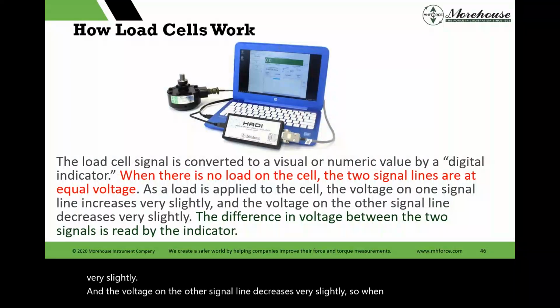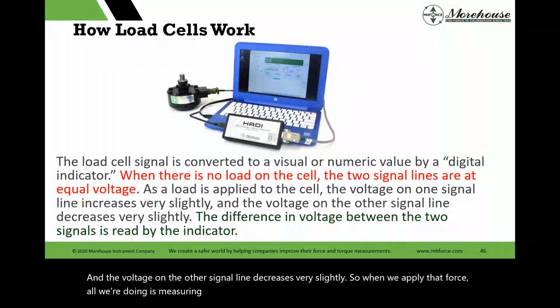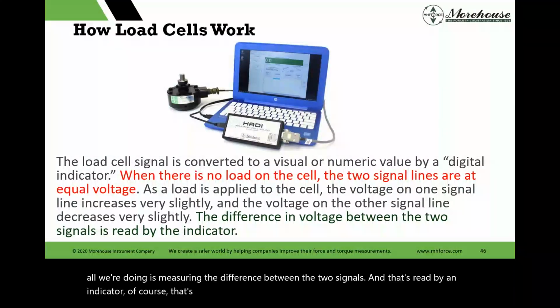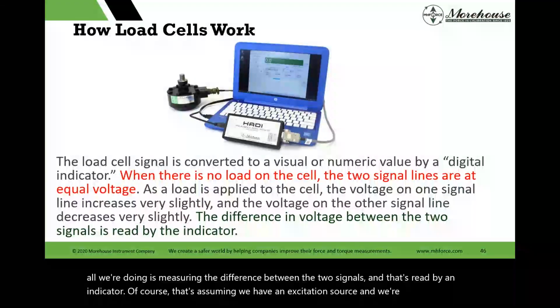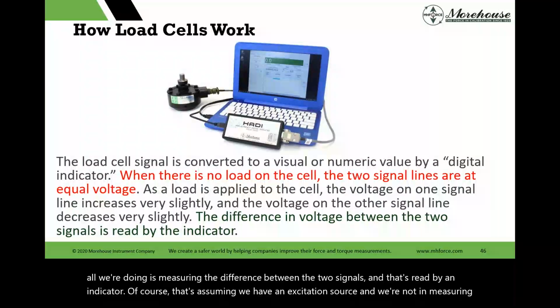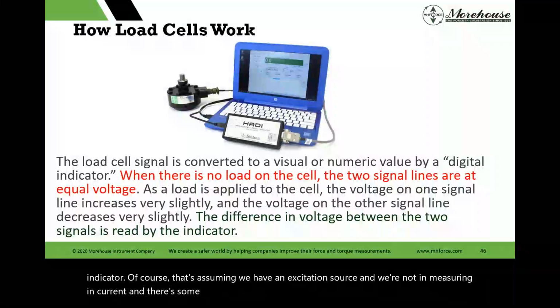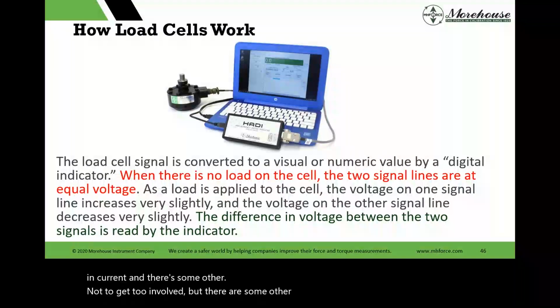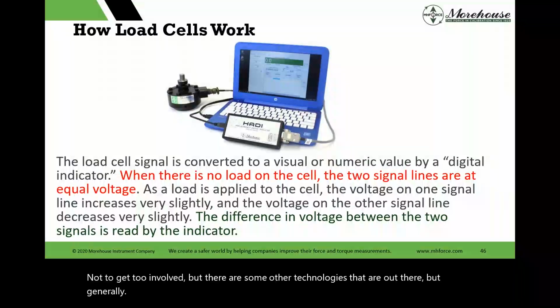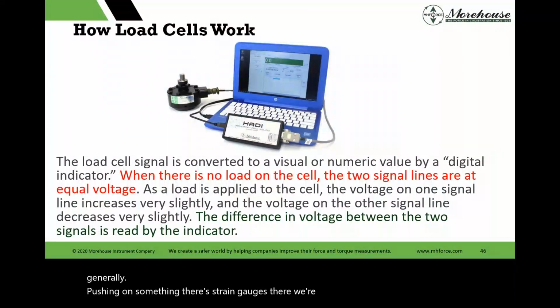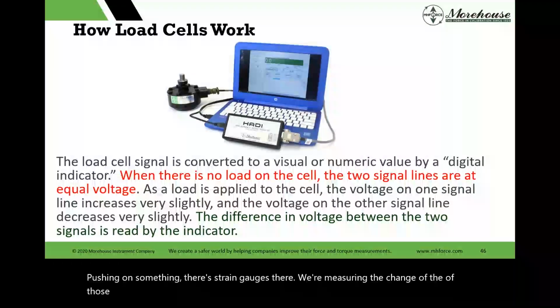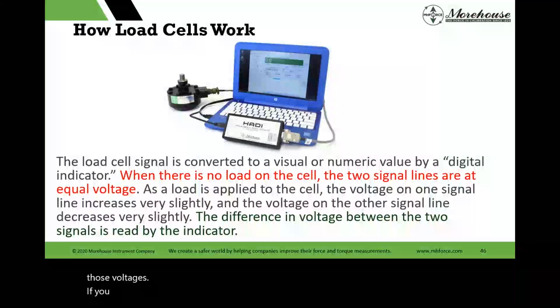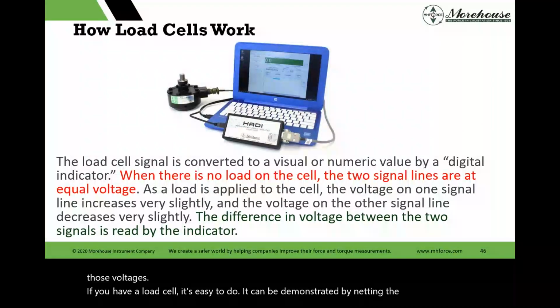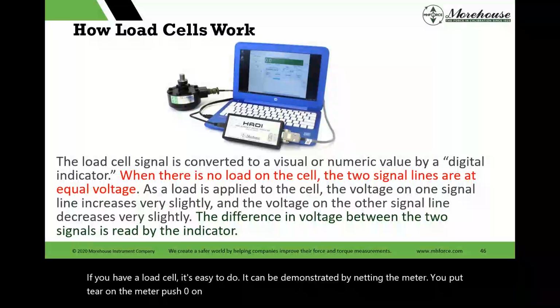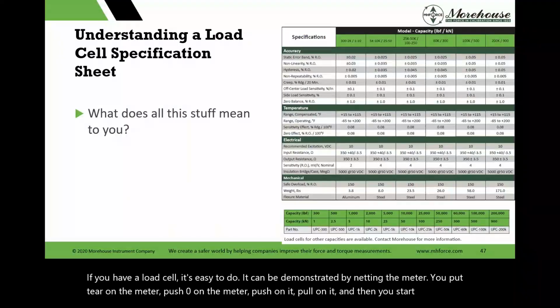So when we apply that force, all we're doing is measuring the difference between the two signals, and that's read by an indicator. Of course, that's assuming we have an excitation source and we're not measuring in current, and there are some other technologies out there, but not to get too involved. Generally, pushing on something, there are strain gauges there, and we're measuring the change of those voltages. If you have a load cell, it's easy to do. It can be demonstrated by netting the meter. You put tare on the meter, push 0 on the meter, push on it, pull on it, and then you start reading change in output.